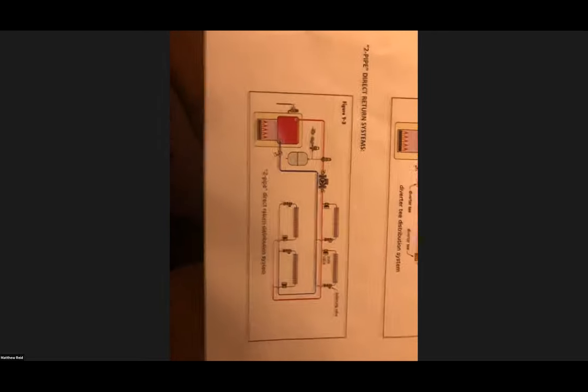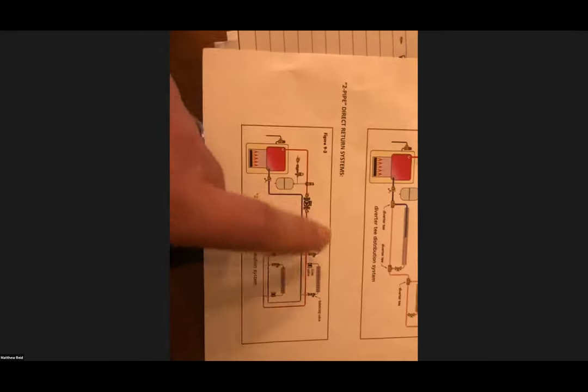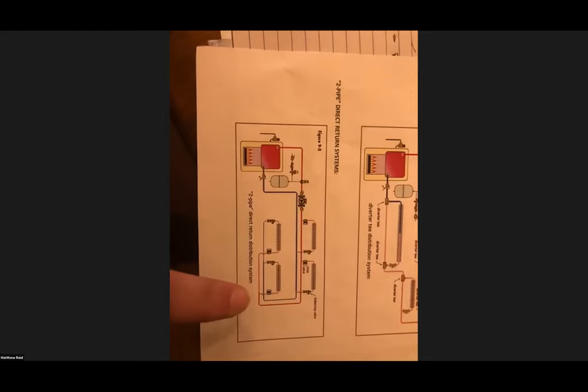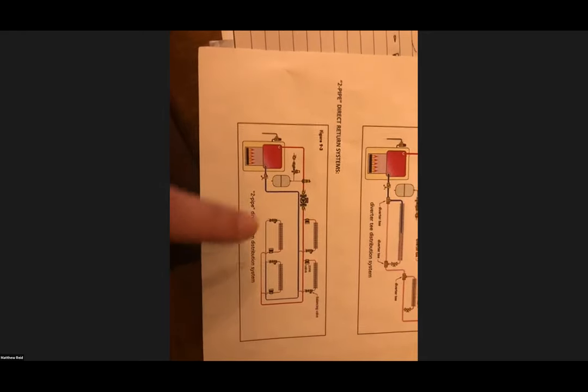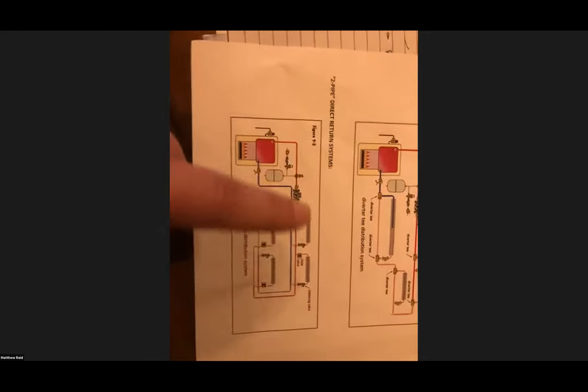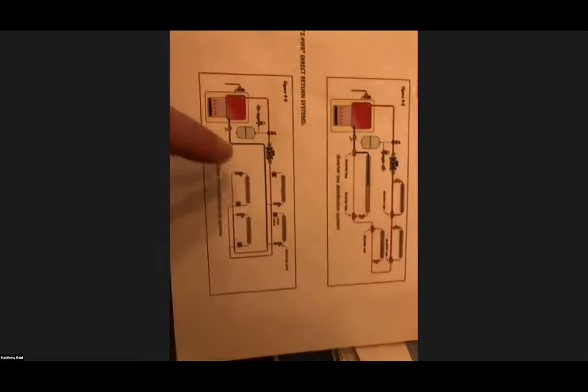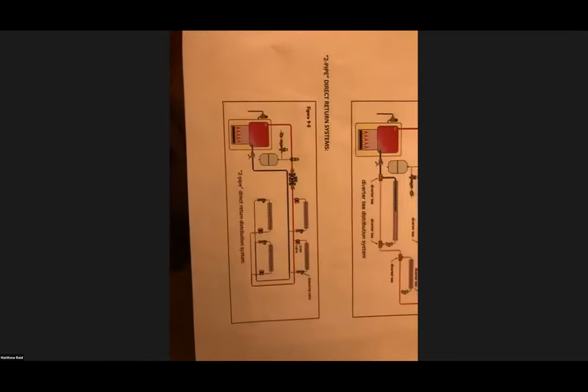We then have our standard two-pipe direct return system where we go out and hit each rad. Each rad is now seeing a direct supply off the main supply line, and then all returning into one common return. The only issue that you might have with these systems, and again, they absolutely work, is that balancing a system like this with balancing valves is required. You have to do some sort of balancing.